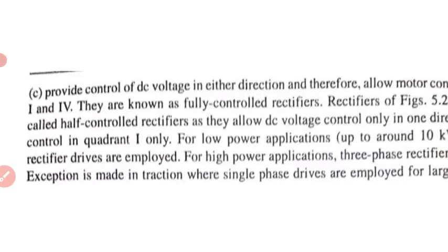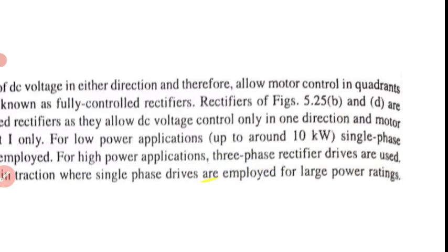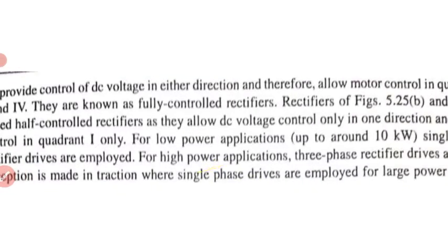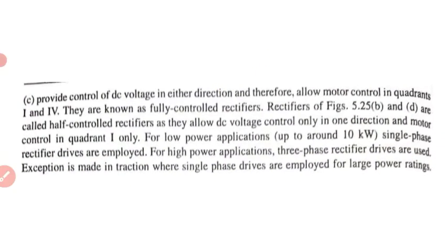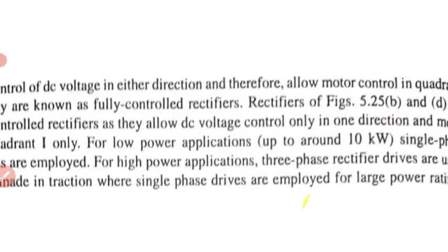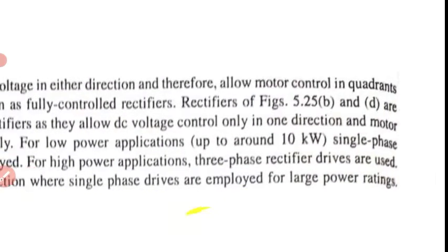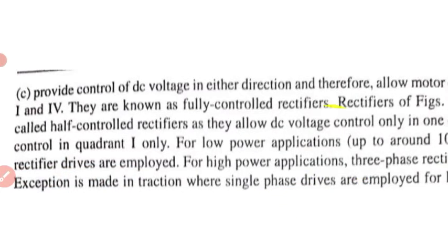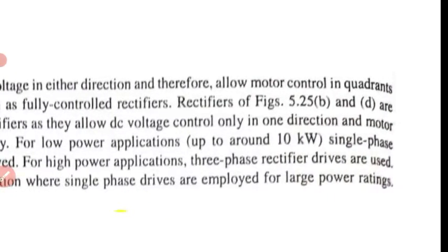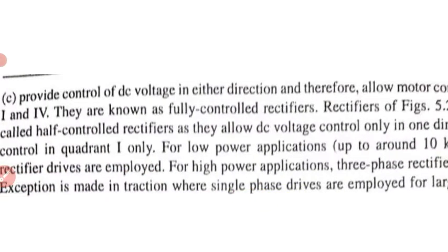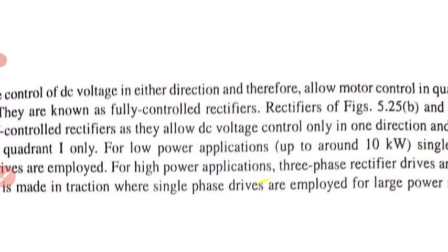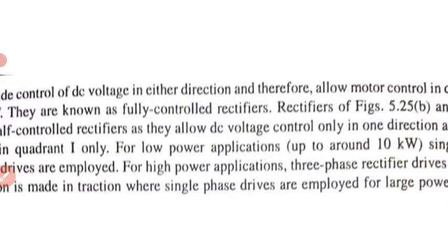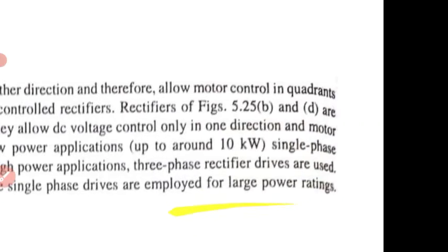Already I have discussed first and fourth, they are known as fully controlled rectifier. Just you have to go through. If it operates in only one quadrant, it is half controlled. These are given for low power application: up to around 10 kilowatt, single phase rectifier drives are employed. For higher, high power applications, three phase rectifier drives are used. Single phase will be used up to around 10 kilowatt. If you want more power, meaning higher motor ratings are required, then we will use three phase rectifier drives.